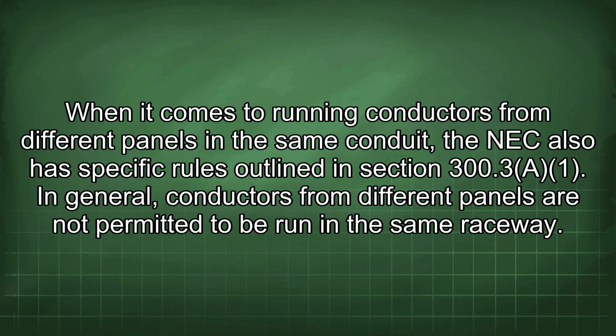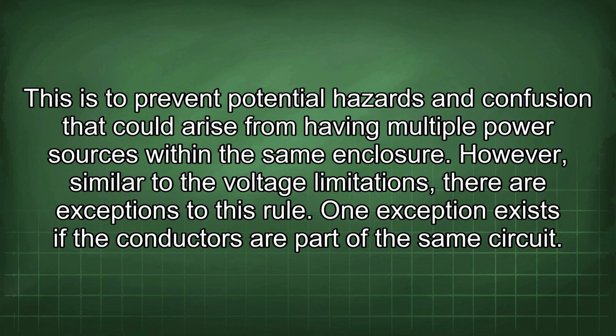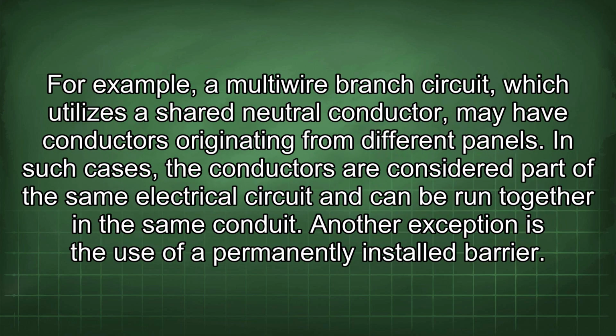When it comes to running conductors from different panels in the same conduit, the NEC also has specific rules outlined in Section 300.3a. In general, conductors from different panels are not permitted to be run in the same raceway. This is to prevent potential hazards and confusion that could arise from having multiple power sources within the same enclosure. However, similar to the voltage limitations, there are exceptions to this rule. One exception exists if the conductors are part of the same circuit. For example, a multi-wire branch circuit, which utilizes a shared neutral conductor, may have conductors originating from different panels.